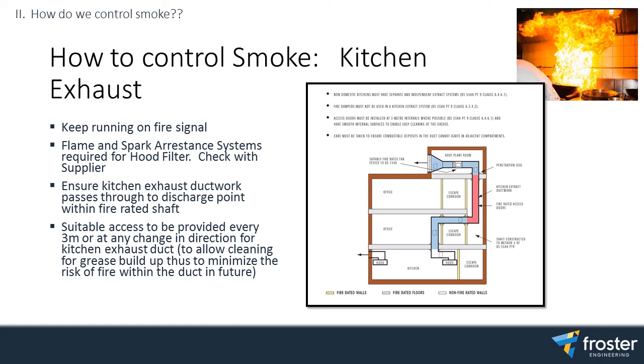Suitable access every 3 meters. This comes up a lot. On that job, we have old hoods. They're taking it all out, they're demolishing it. The kitchen exhaust system's perspective-wise well over here, crossing over other tenancies down on ground. The developer wants to master plan it and just kind of deal with this separately. So what we're doing there is we're actually removing all this kitchen exhaust ductwork, relocating that fan deck over here, and creating a new common riser. So that riser, it is in a masonry shaft. We need to fire wrap that ductwork going up, but also we need to provide access every 3 meters.